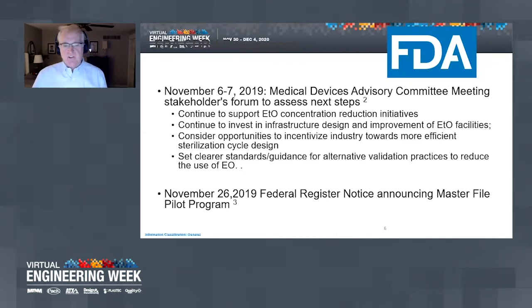So running in the background to all this was the concern and the question as to what would EPA do against EO. Now, picture this, we're with the current administration, and there was a fair amount of turnover in leadership of EPA and the public outcry. This is all pre-COVID. EPA was really set to change their EO limits and basically move it to essentially zero emissions for medical device sterilizers. Okay, that's the details in their Federal Register notice, and that decision is coming later in 2021, I think in part because of the administration and in part because of COVID, because if they were continuing to shut down sterilization facilities, there'd be even less PPE.